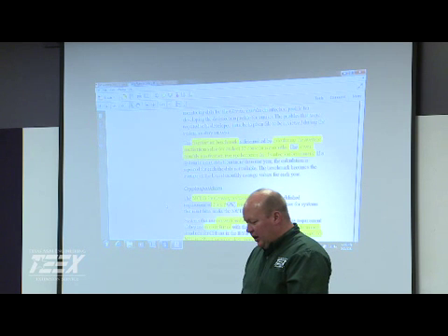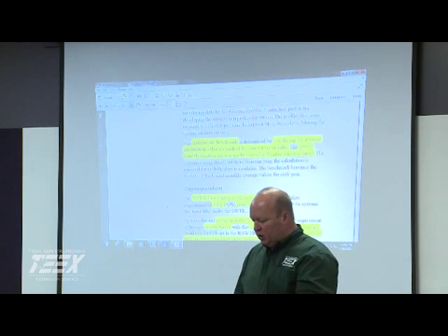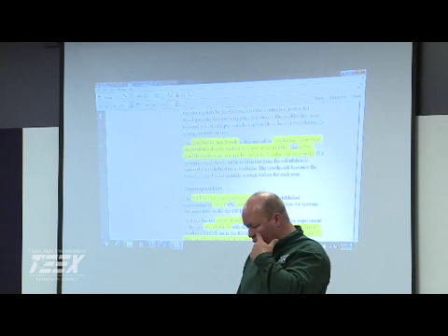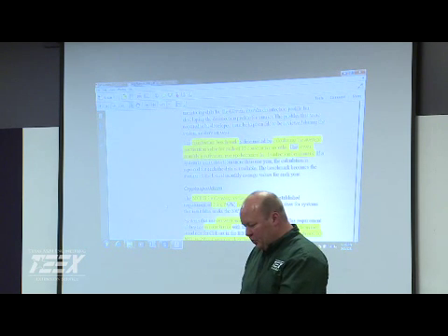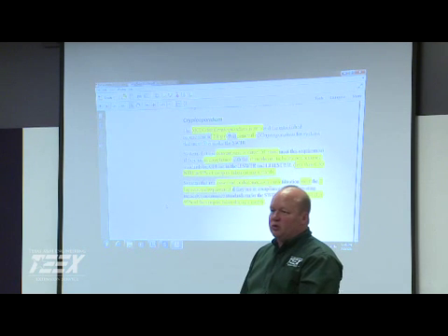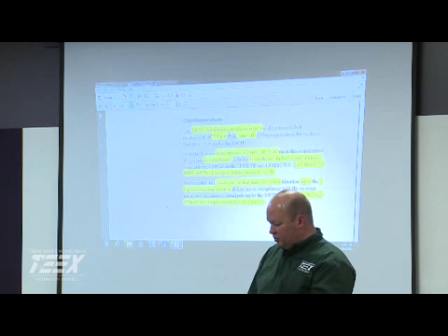And then it gets into, again, all the legal fun stuff. Then your average inactivation value is going to be for the 12 months, and you're looking at what's the lowest value you reach, and that's going to be your benchmark. And then for crypto, obviously our goal is 0, but they do want a 2-log removal if you're under the surface water treatment rule.